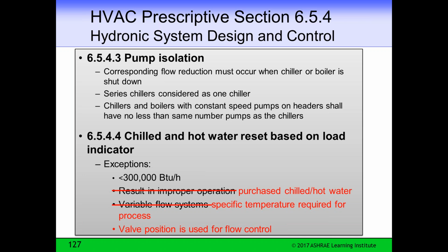Chillers and boilers with constant speed pumps on headers shall have no less than the same number of pumps as the chillers, so that we can turn off a pump each time we turn off a chiller or a boiler. Chilled and hot water reset based on load indicator.